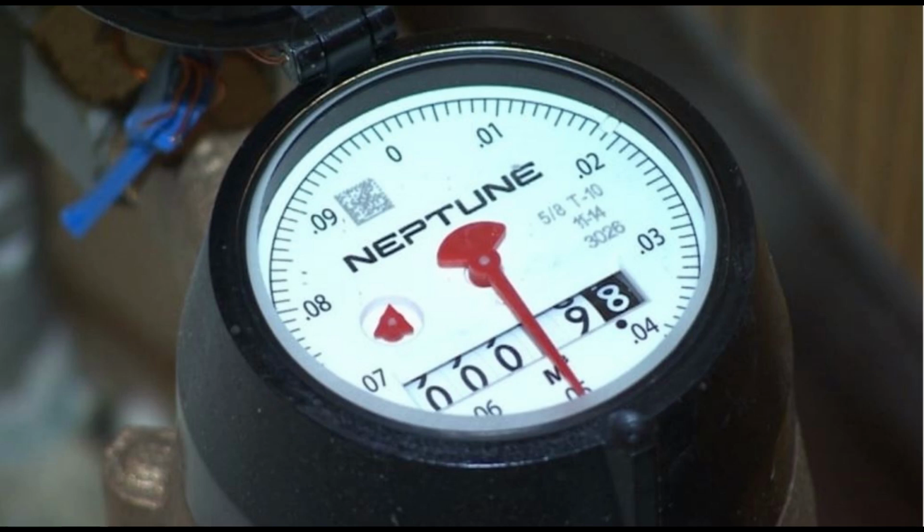Turbine meters are generally available for 1+1/2 in, 38 mm, to 12 in, 300 mm, or higher pipe sizes. Turbine meter bodies are commonly made of bronze, cast iron, or ductile iron. Internal turbine elements can be plastic or non-corrosive metal alloys. They are accurate in normal working conditions but are greatly affected by the flow profile and fluid conditions.